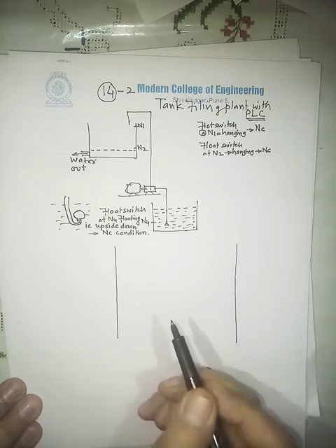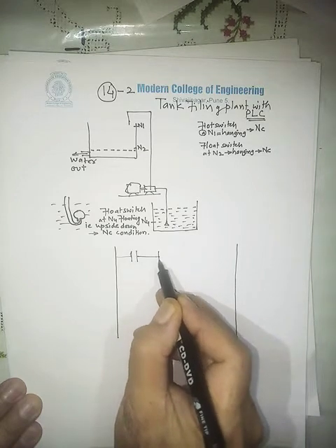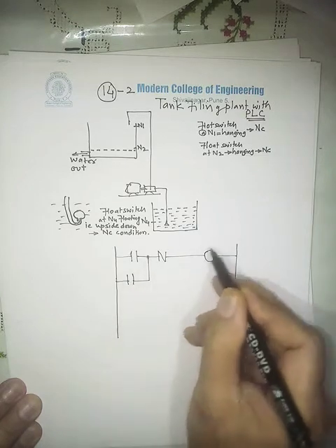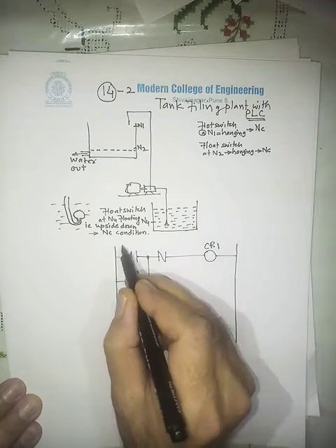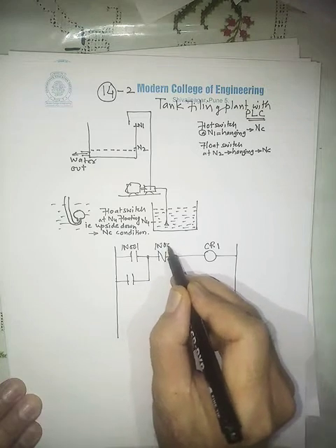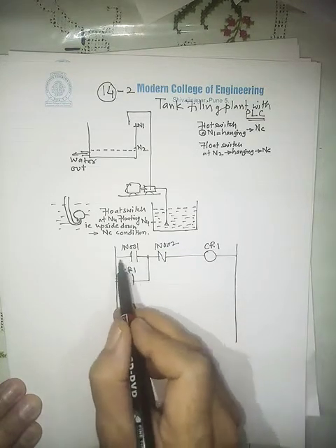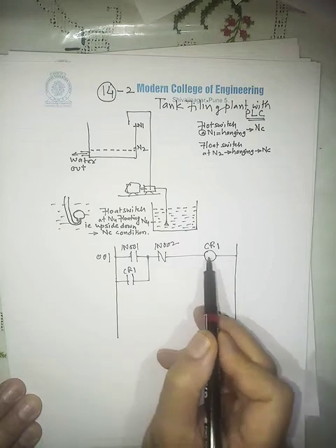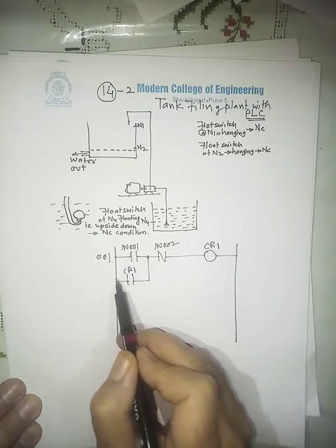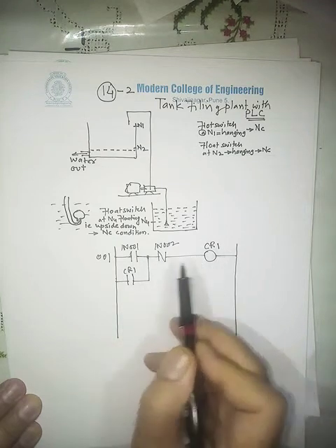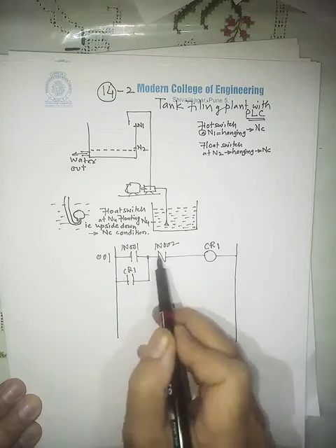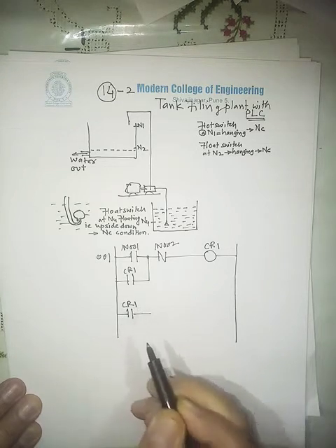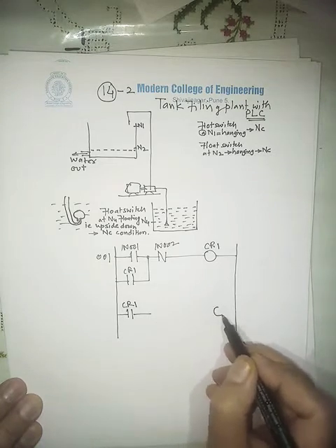First I will draw the latch circuit to keep the pump and motor continuously running. This is the latch circuit. Let's say this is start switch 1 — contact 001 — and this is stop switch 1 — contact 002. This is CR1 coil and this is CR1 contact. Once I press the start switch, supply is through and the coil gets activated, causing the contact to go high. There is now an alternate path of power, so if I release the start switch it will not go low — it is latched and remains on. Here I will use one more switch, CR1, connected to the motor for the pump.